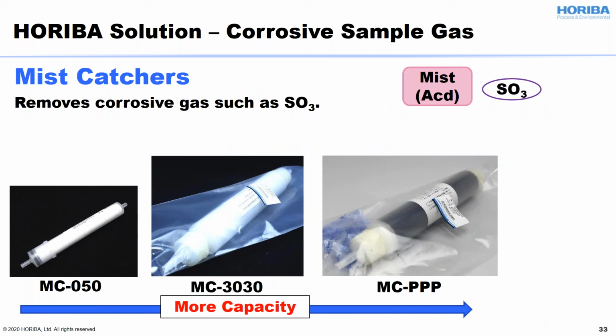Okay, in a sample conditioning system, we also need to deal with those corrosive gases, and ideally we need to get rid of all the harmful corrosive gas in a sample system. We want to carry the sample gas into the analyzer, and that gas should be as clean as we can make it. So the sample gas conditioning system will work for it.